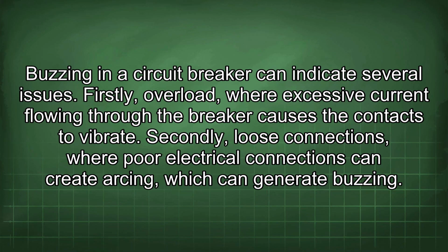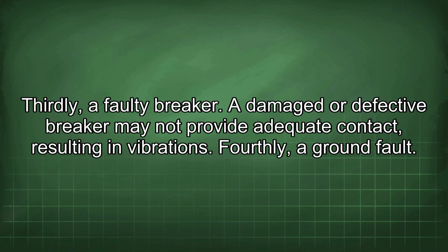Buzzing in a circuit breaker can indicate several issues. Firstly, overload, where excessive current flowing through the breaker causes the contacts to vibrate. Secondly, loose connections, where poor electrical connections can create arcing, which can generate buzzing. Thirdly, a faulty breaker. A damaged or defective breaker may not provide adequate contact, resulting in vibrations.